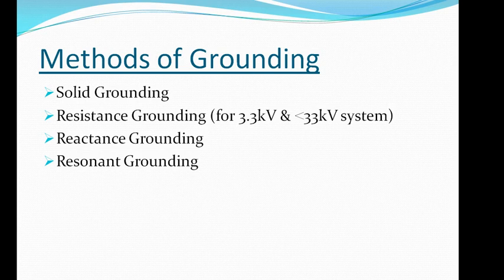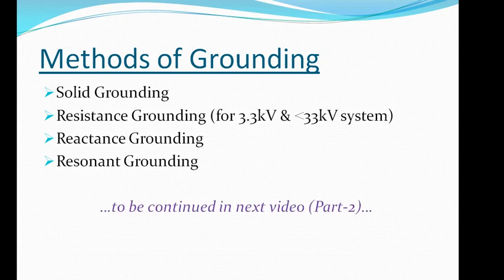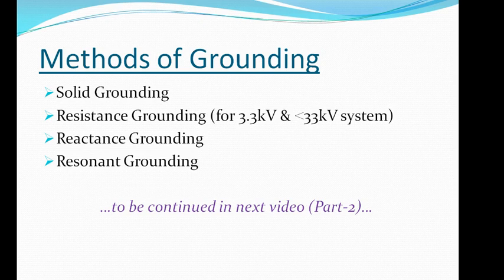Resistance grounding is used between 3.3 kV and 33 kV systems and is used for less capacitive circuits. Reactance grounding is used for circuits where high charging currents are involved, such as power transmission lines and underground cables; this type provides additional reactance which neutralizes capacitive currents. Finally, resonant grounding uses an arc suppression coil called a Petersen coil, which controls the earth fault current to ground.